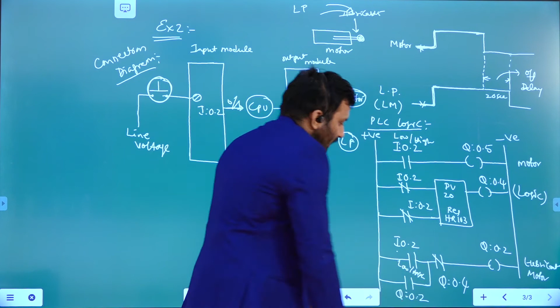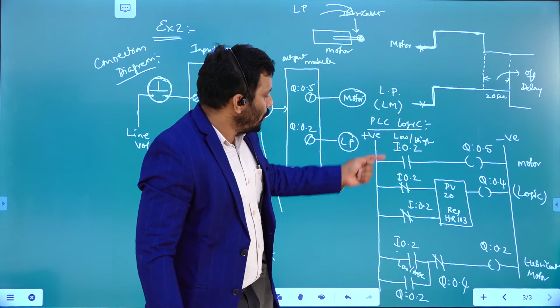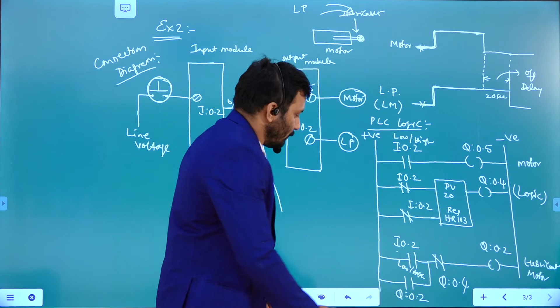Whenever it is sealed, even though this input is low, if you switch this off after some time, this input is low, and once again this is also low. If it is low, what will happen? The motor is going to be off. But this lubrication pump is not going to be off. Why? Because this is sealed. Previously we discussed this. Even though this is low, this is already high, and that high is going to become the input to this particular sealing circuit.